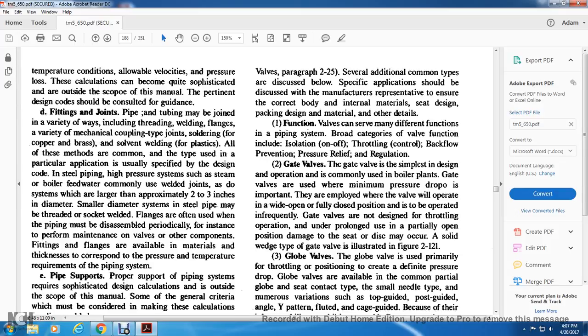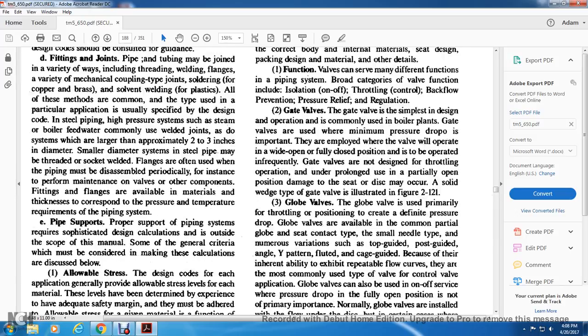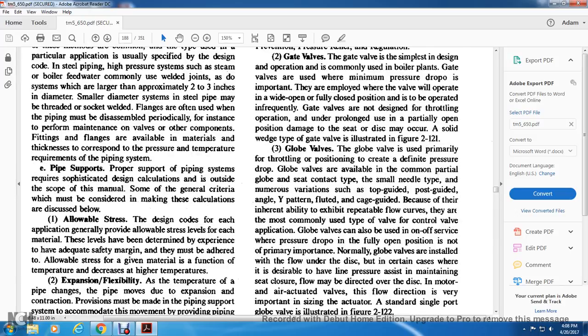The gate valve. The gate valve is a simple design commonly used in boiler plants. To achieve the minimum pressure drop, it is important that the valve is operated in the wide open or fully closed position. Gate valves are not designed for throttling operation in a prolonged, partially open position. Damage to the seat and disc may occur. A solid wedge type of gate valve is illustrated in Figure 2-121.